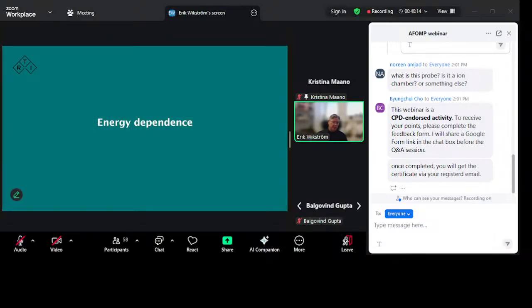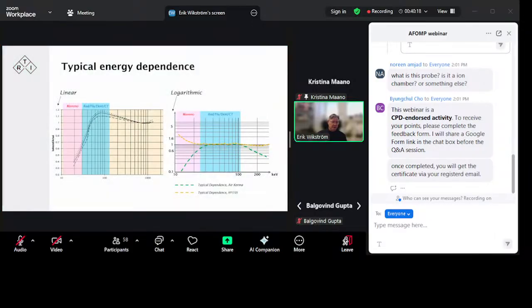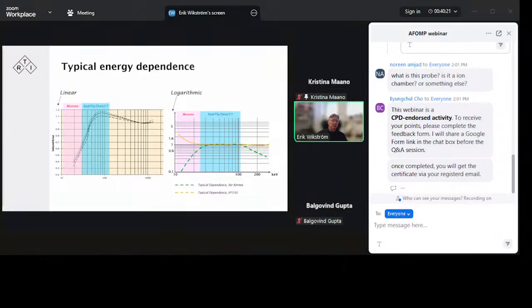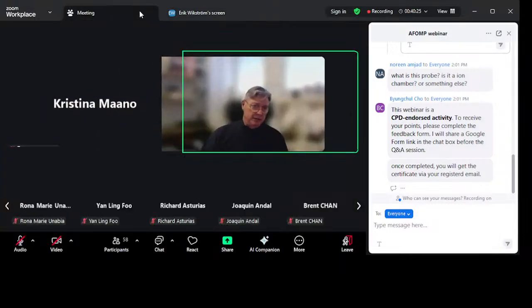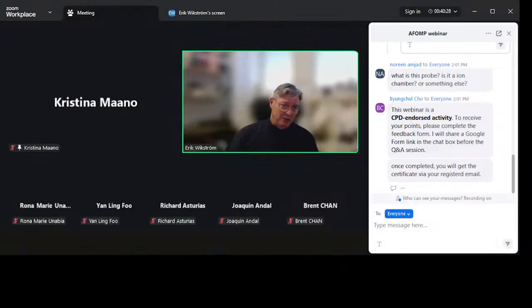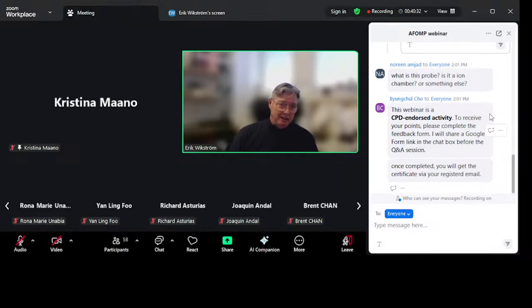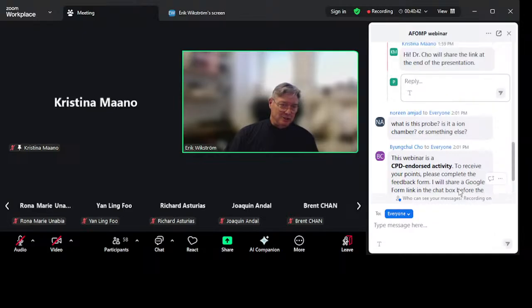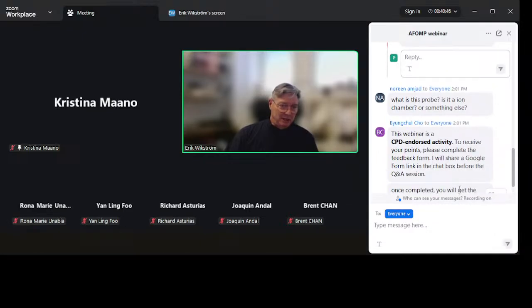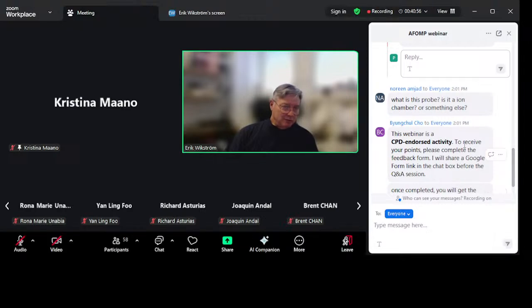Just to give you a better idea again, energy dependence. So this is just typical curves of energy dependence that we see from other meters in the market. And there are different scales here also. Here's a linear scale, which produces this curve. And then you may see also logarithmic curves that look like this. So here you see that this is one where the reading is proper, and it happens only up here, which is around 800 keV, and down here, which is 20, 30, 40, 50 keV, which is up here. That's when it shows the right value. For other values, we need to compensate.